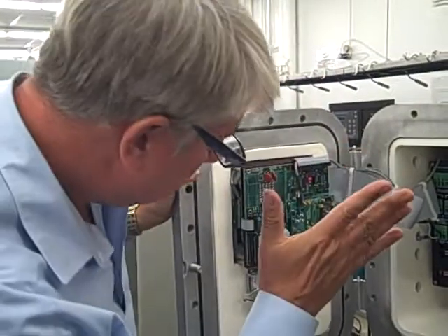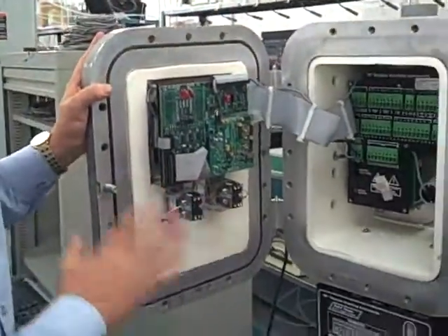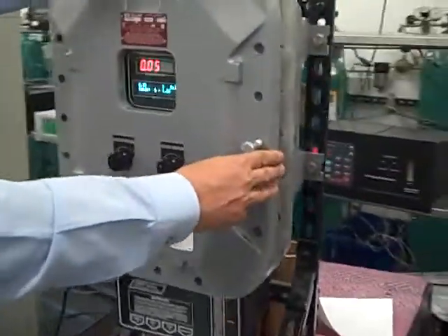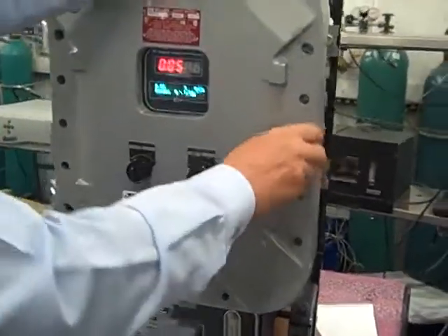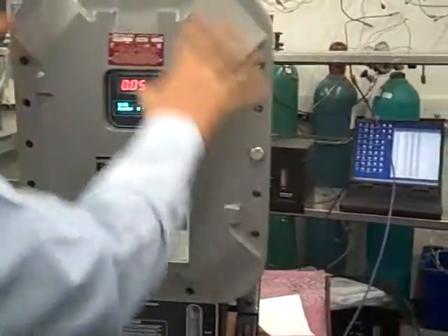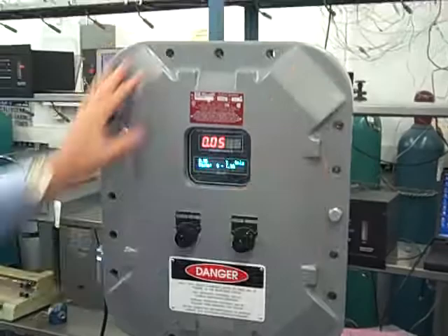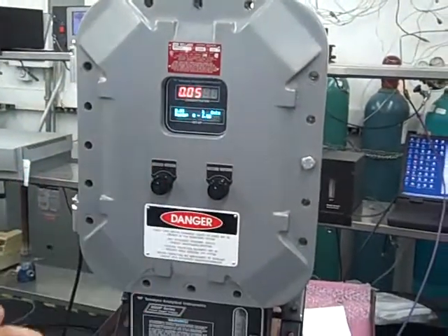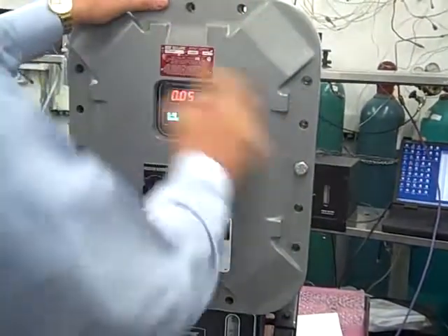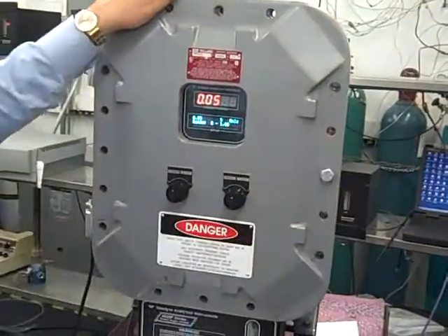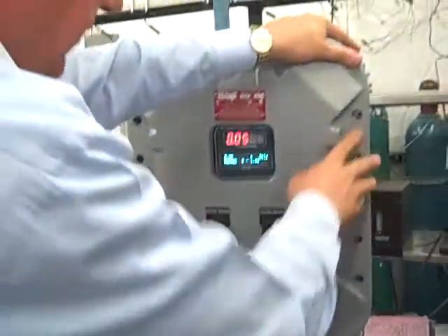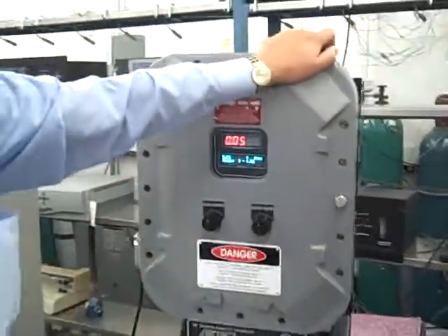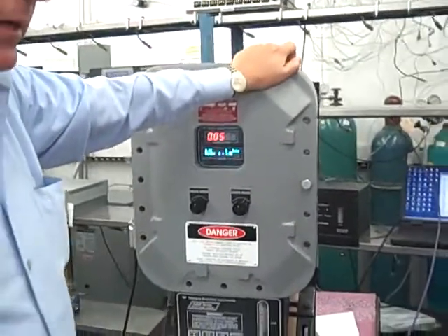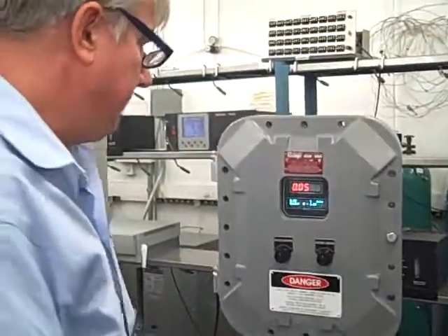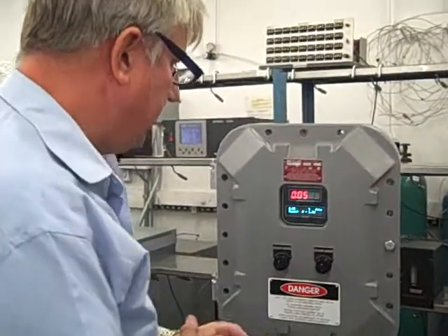And these are the explosion-proof switches. Now, of course, if you're operating this in a hazardous area, I'm sure all of you know that all the bolts must be installed for it to be fully operable. Do not try to just get by on one bolt. And if you need to open the unit, the area will need to be declassified temporarily. Okay? So that's the basic setup of the unit.